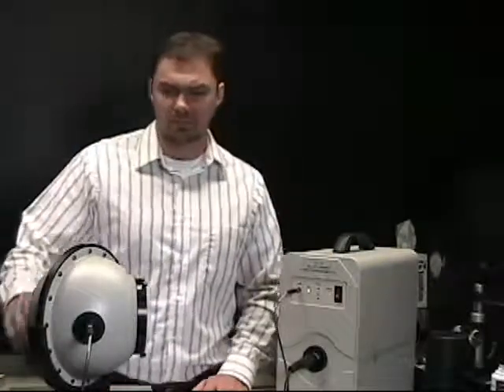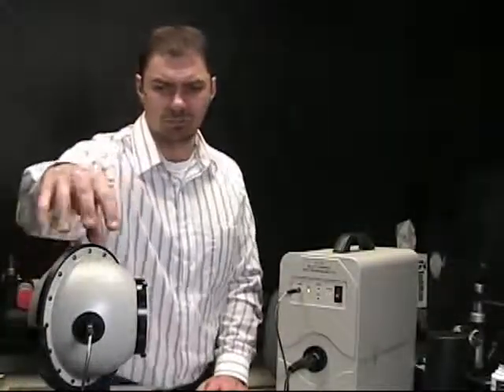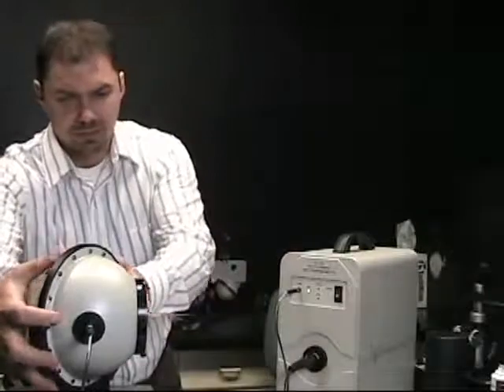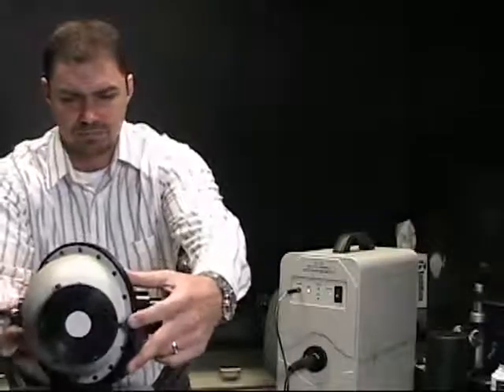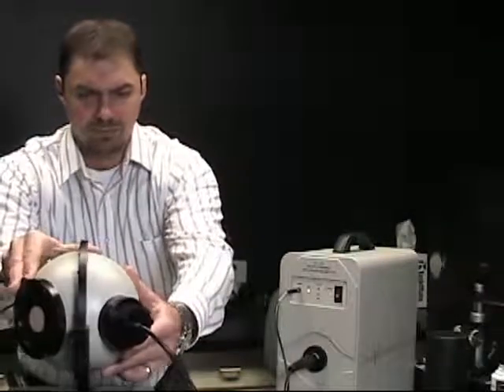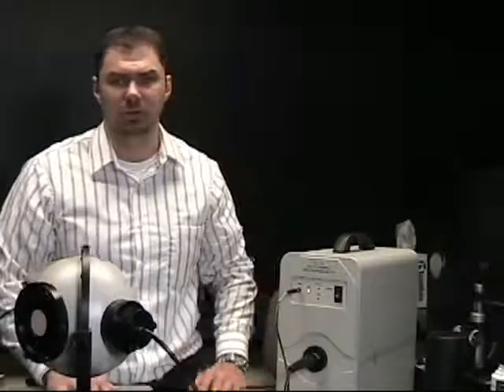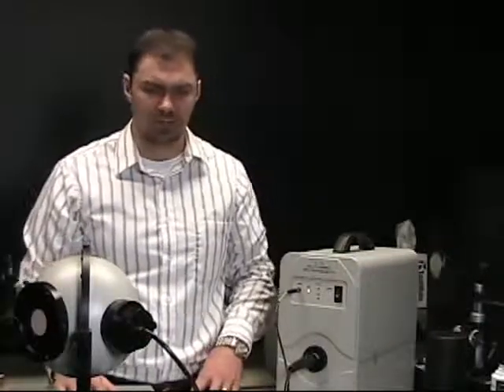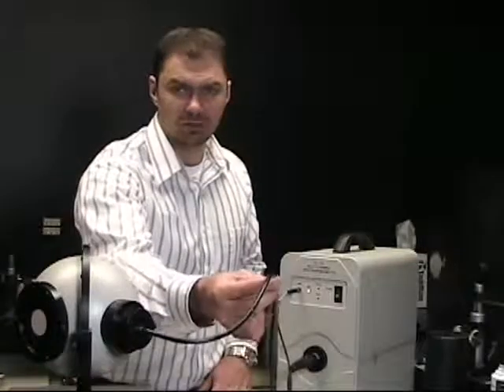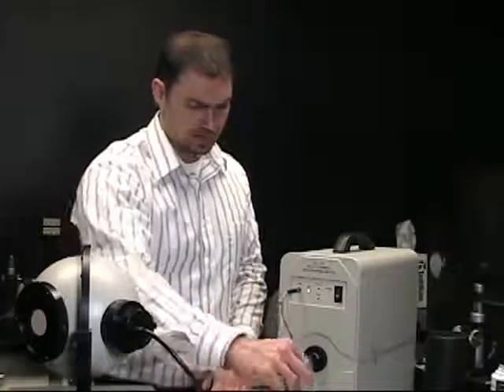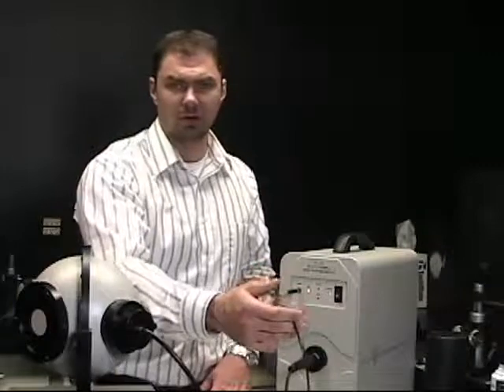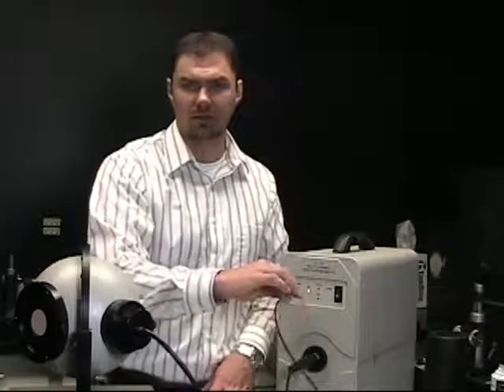To begin with, we're going to do the radiant intensity measurements and the total luminous flux measurements, both with the same input optic. We're going to use our 6-inch integrating sphere, and we're configured right now for either irradiance, radiant intensity measurement, or total luminous flux measurement. I have a 3mm measurement fiber, and also our 600 micron internal reference lamp fiber.